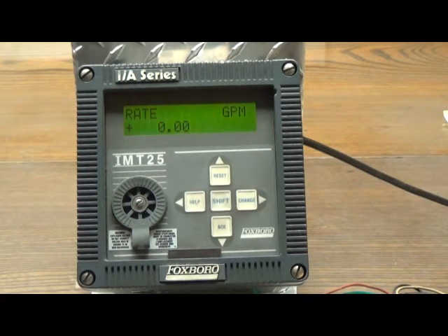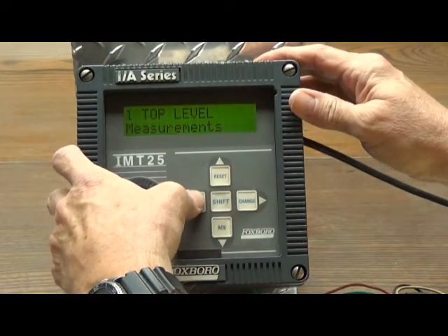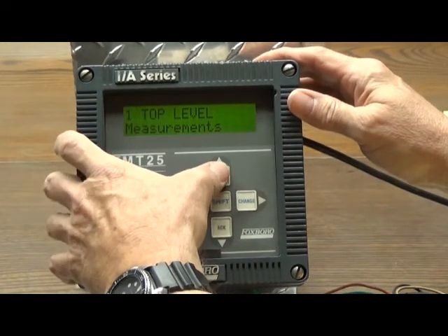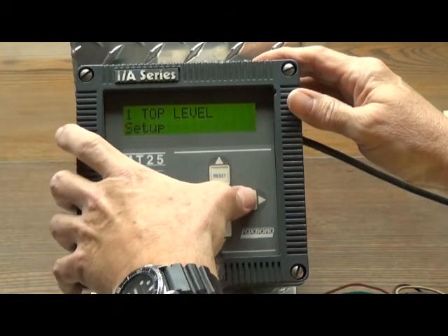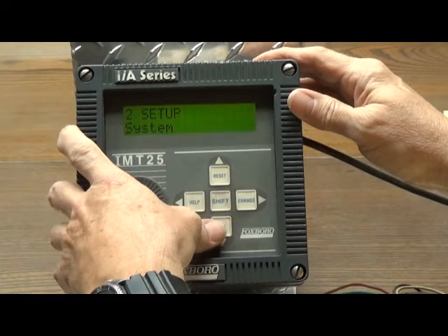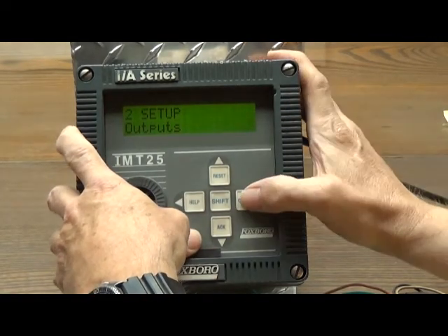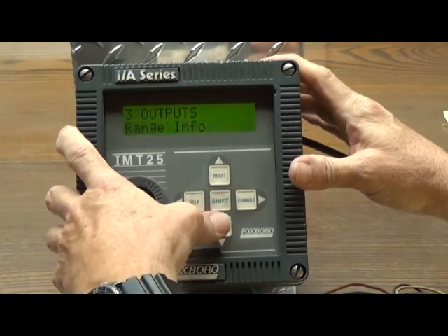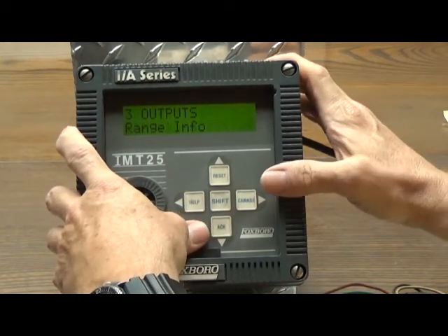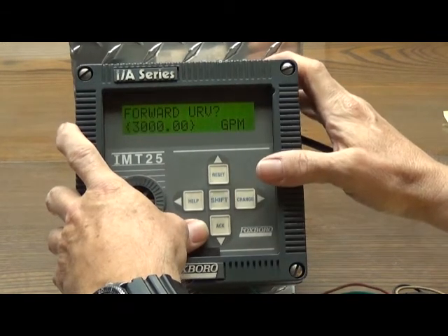Now we're going to change the output range set into the instrument. The procedure is as before: help or left arrow to measurements, reset up arrow to setup, change right arrow to system, ACK down arrow to outputs, change right arrow to output mode, ACK down arrow to range info, change right arrow to the URV.